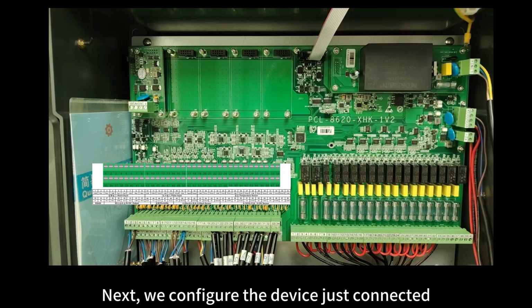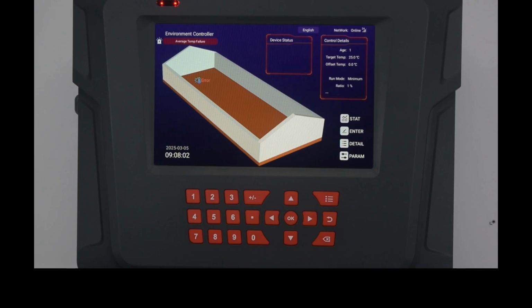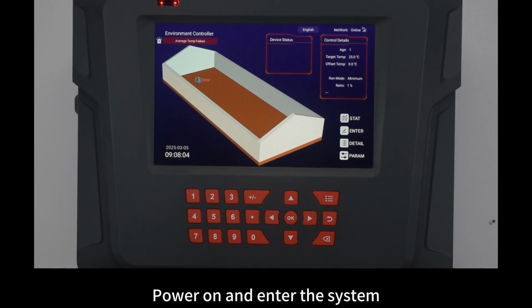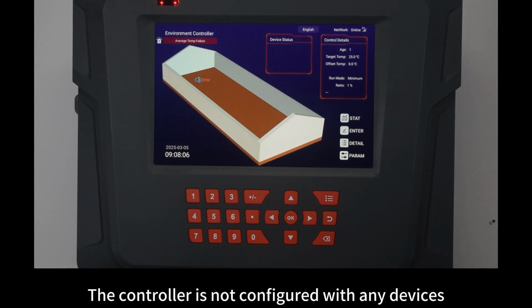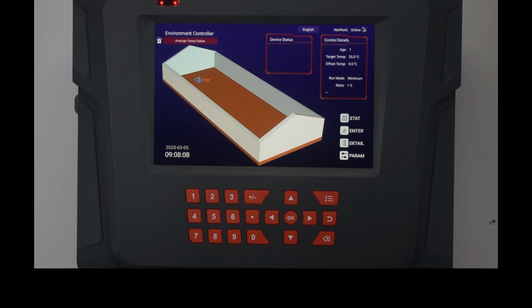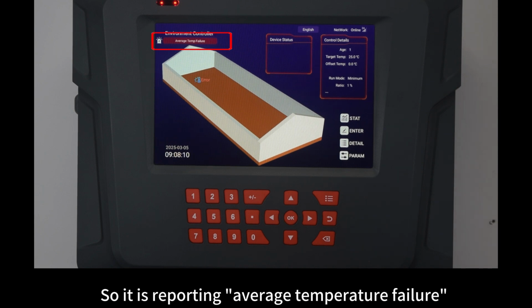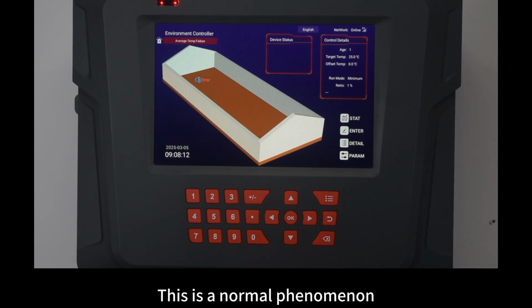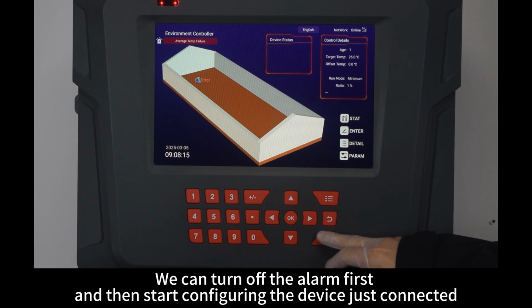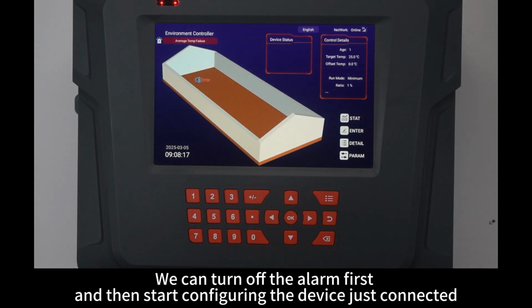Next, we configure the device just connected. Power on and enter the system. The controller is not configured with any devices, so it is reporting average temperature failure. This is a normal phenomenon. We can turn off the alarm first, and then start configuring the device just connected.